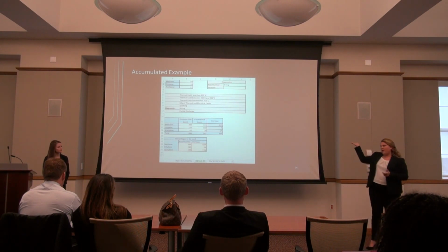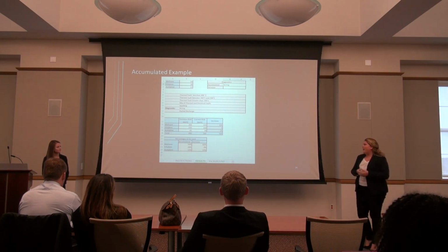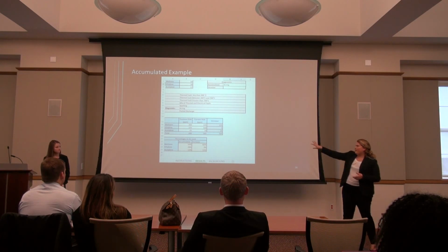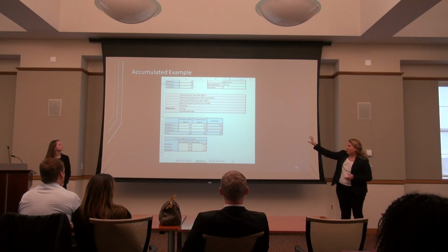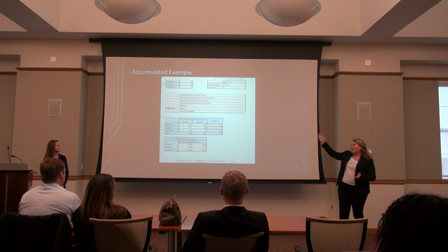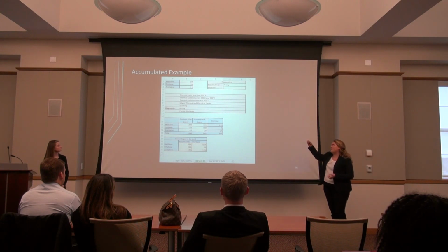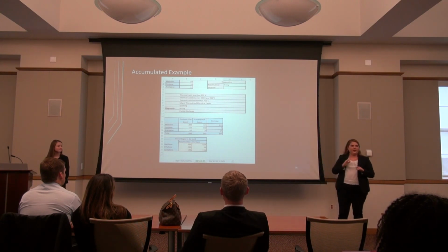This can be done in honestly less than a minute. Here's an example for the accumulated one: the user inputs the results from the previous DGA and the current DGA, the percentages are given, then you put them at the top, and we get that the diagnostic is working. That can be written down at the top right table.